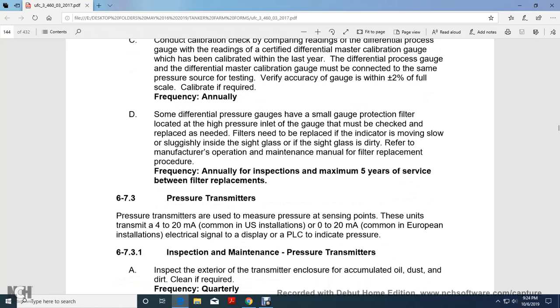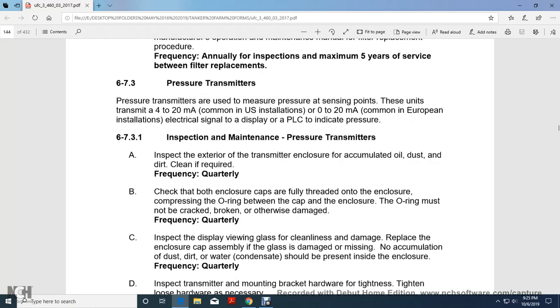Some differential pressure gauges have a small gauge protection filter located at the high pressure inlet. The filter must be checked if the indicator plate is moving sluggishly inside the gauge sight glass, or if the glass is dirty. Refer to the manufacturer's operation and maintenance manual. Filter replacement is required. Frequency: annually for inspection, with a maximum of 5 years of service between filter replacements.